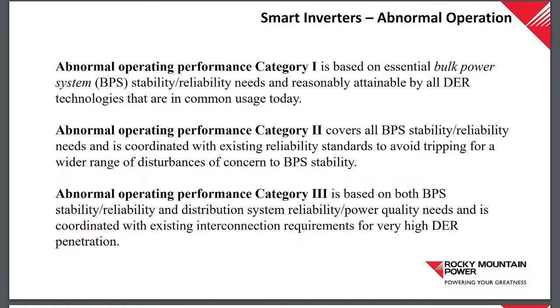And so these new inverters have these categories for abnormal voltage, so you get category 1, 2, and 3. And again, it's something that needs to be selected. They come pre-programmed, every inverter that meets that new certification will have the capability to do category 1, 2, and 3. We just need to select which one we want to incorporate into our settings.